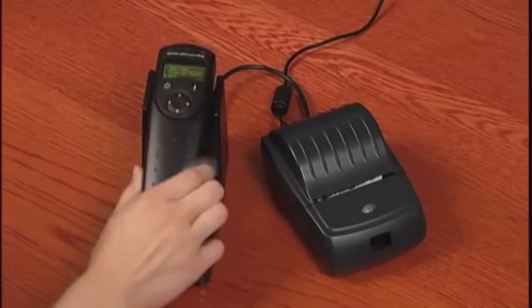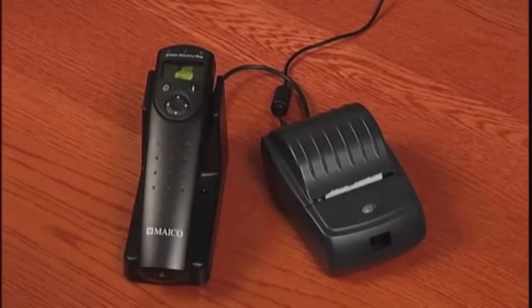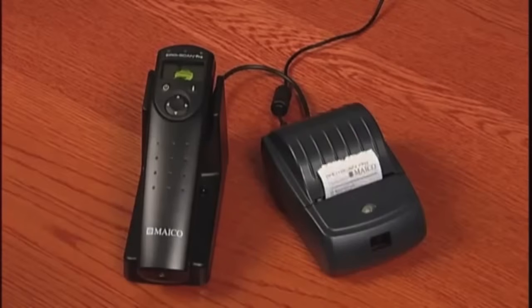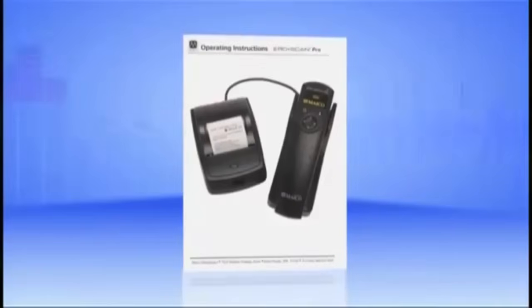Once the test results are printed, they're flagged for deletion. When you run the next test, the previous results are then deleted. This is a fail-safe so that if there's a problem printing, the problem can be corrected, and then the test results can be printed again before you run the next test. To print all test results, place the Ero Scan Pro in the printer cradle. All of the saved tests will print automatically. For more information on printing, please refer to your operating manual.